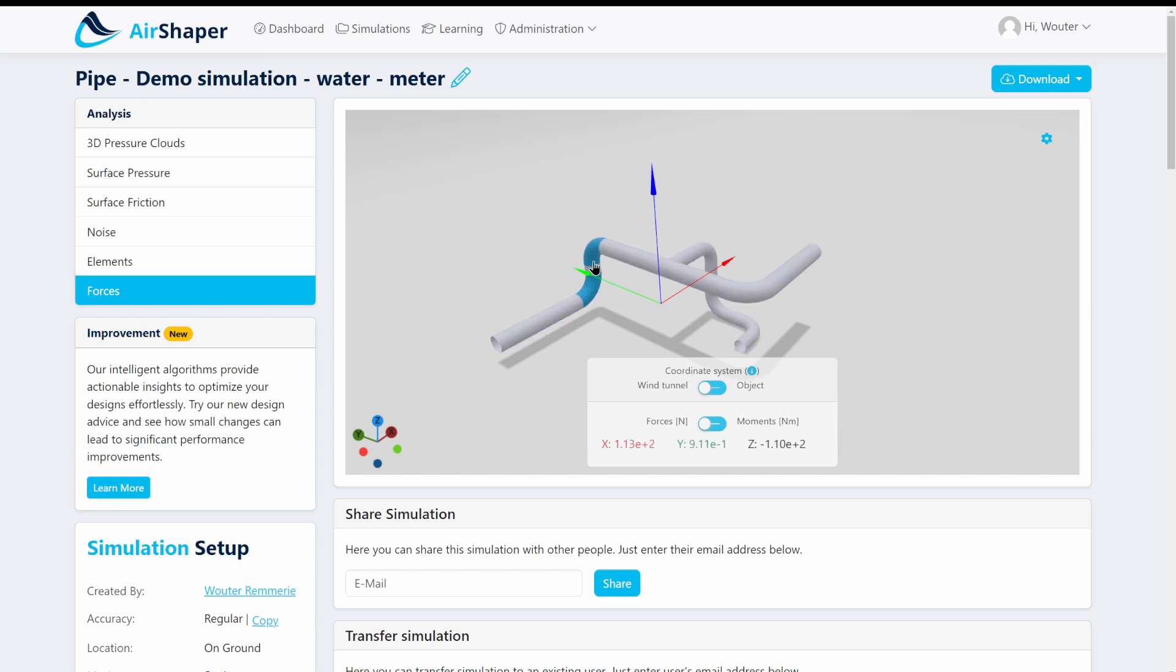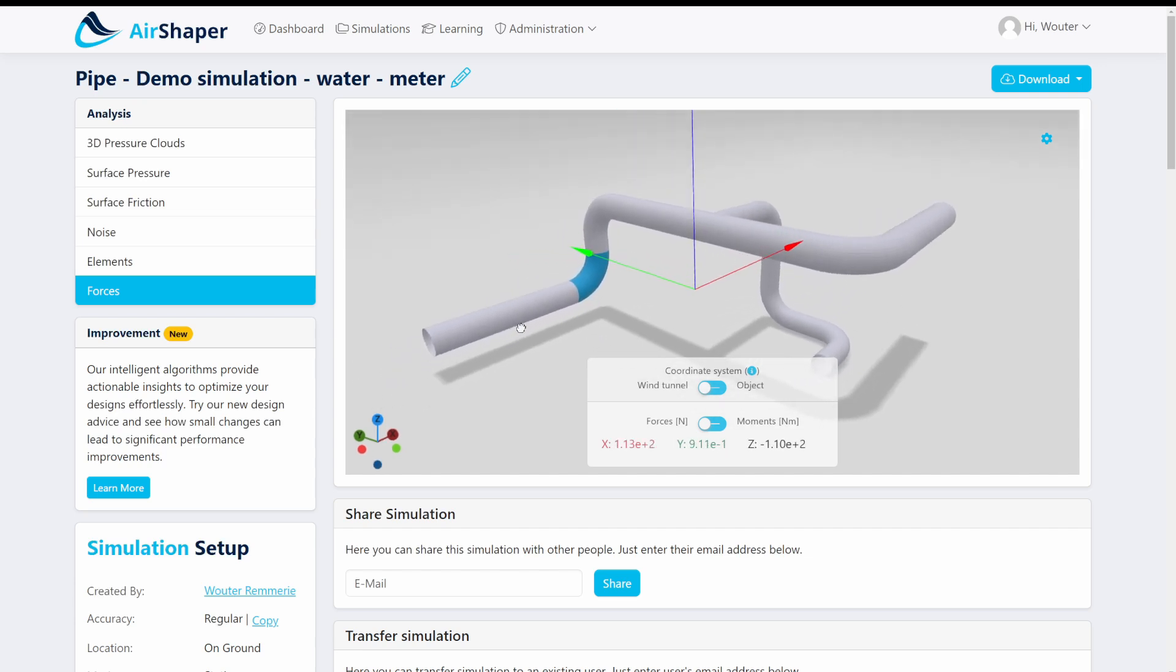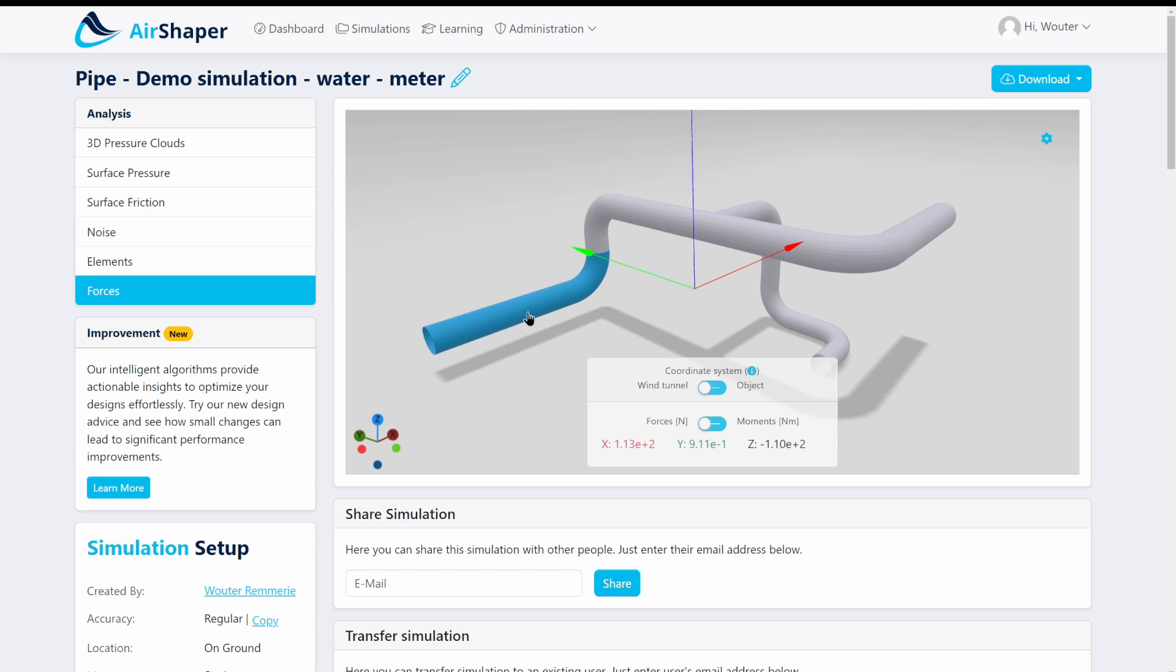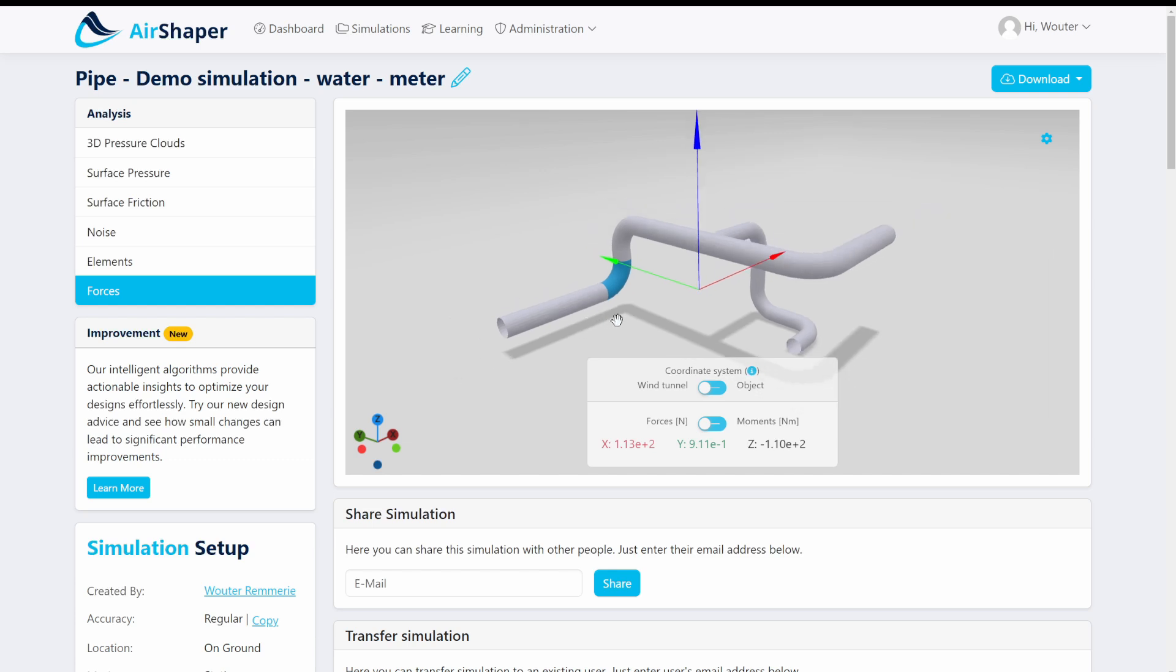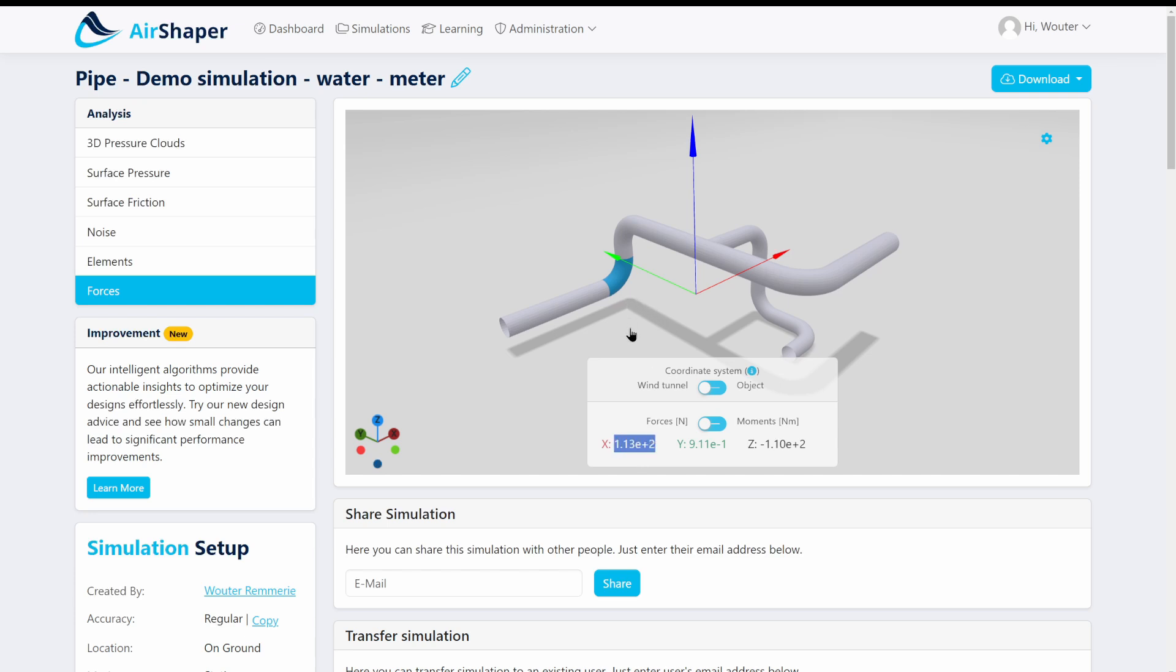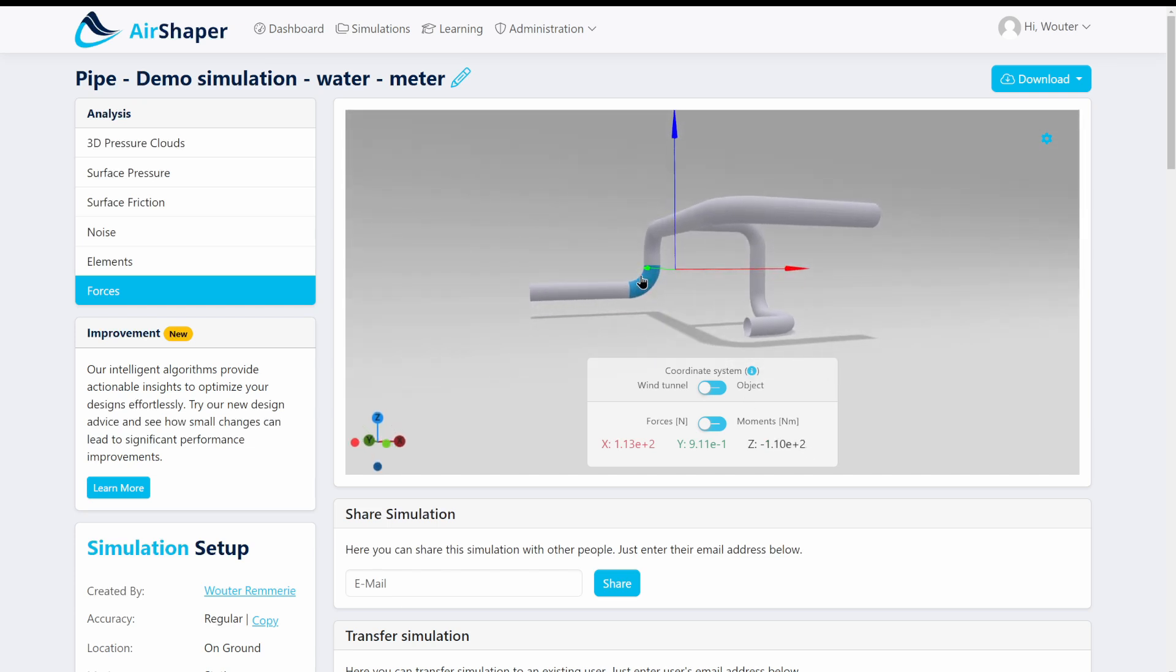You'll notice that you get quite a lot of forces on these elements because as you can imagine if there's a large flow rate of water that needs to be pushed into another direction by 90 degrees then you have a lot of reaction forces on these elements. So in this case you'll see that along the x-axis for example you get quite a big reaction force so there's a force of 130 newtons pushing this way and also 110 which is basically almost the same because the resulting force will be pushing at 45 degrees which means a positive x and along the z-axis a negative z, so a force like this acting and causing a reaction force on that system.